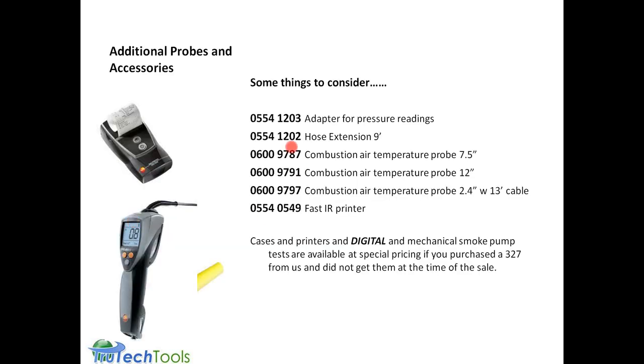And we talked about several different accessories that are available. The adapter for pressure reading, there's a hose extension available. There's a combustion air temperature probe available in different lengths, and an IR printer. But right now you're getting the IR printer with the meter for that $900 price. There's also a mechanical smoke pump available, and if you wanted to get a mechanical smoke pump at a special price from us, if you didn't purchase one either and you feel you need one, that would be mainly for people doing oil burner work.